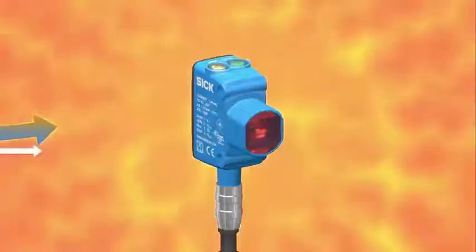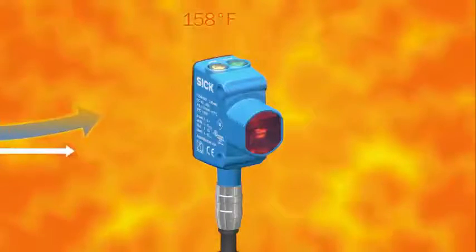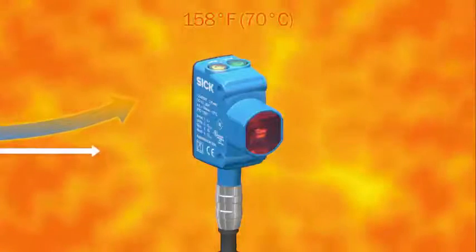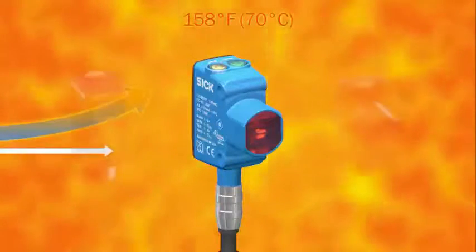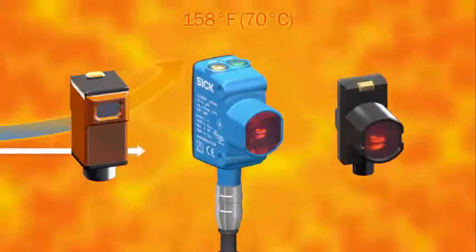This family of sensors can be used in environments of up to 158 degrees Fahrenheit or 70 degrees Celsius. It has built-in self-protection technology that will power down the sensor when it operates above the specified temperature range.